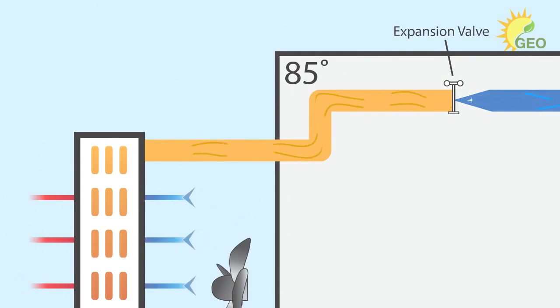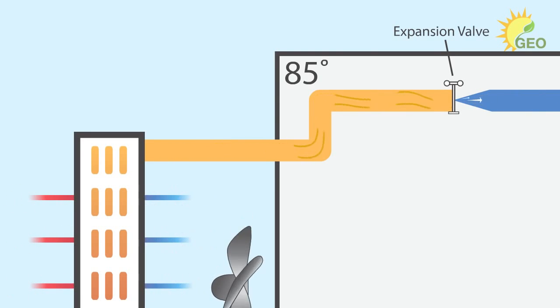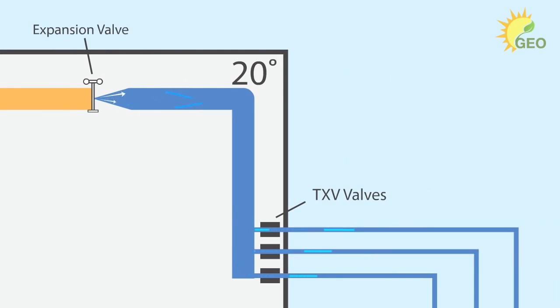As the refrigerant leaves the coil, it condenses back to its liquid state and moves toward the expansion valve at 85 degrees. The expansion valve is basically like a dam with a small hole. When the refrigerant passes through the expansion valve, the pressure rapidly decreases and the temperature falls to 20 degrees.